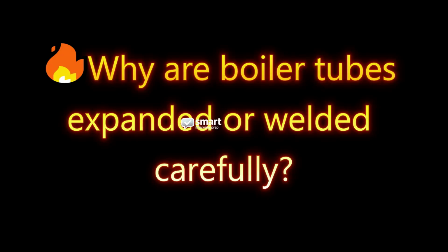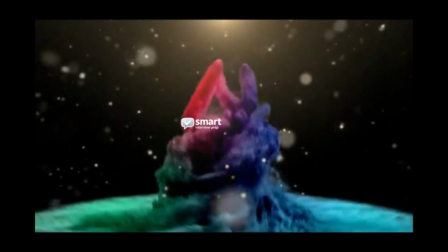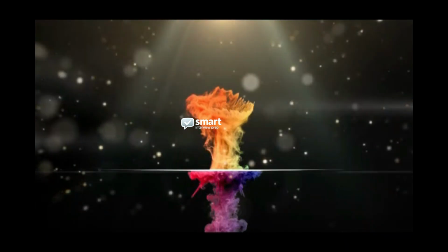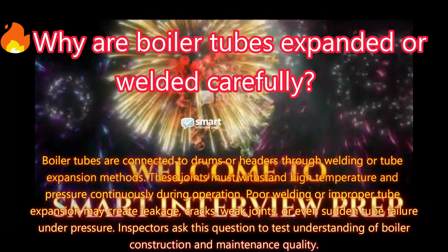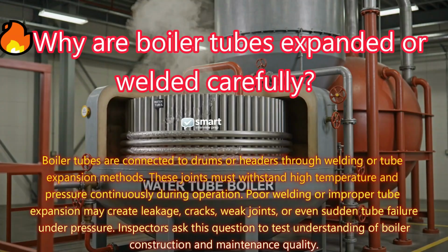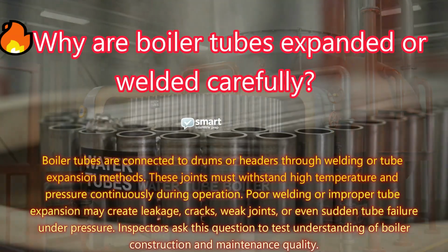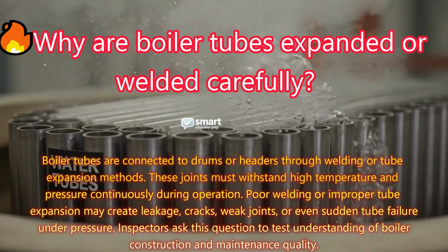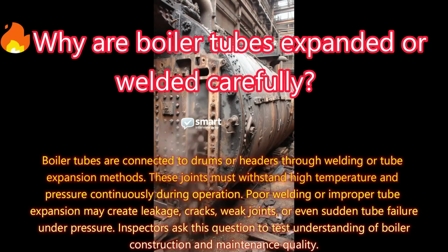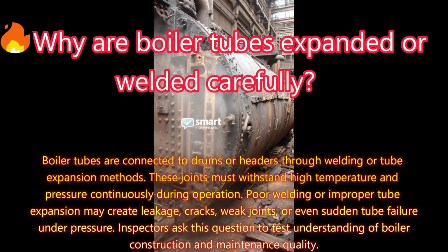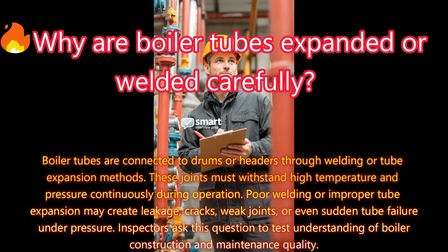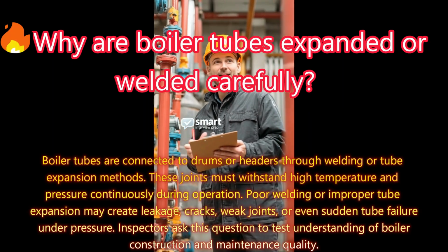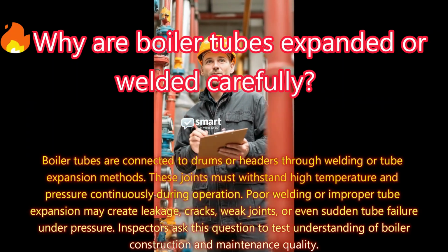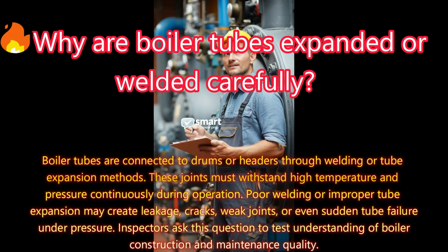Why are boiler tubes expanded or welded carefully? Answer. Boiler tubes are connected to drums or headers through welding or tube expansion methods. These joints must withstand high temperature and pressure continuously during operation. Poor welding or improper tube expansion may create leakage, cracks, weak joints, or even sudden tube failure under pressure.